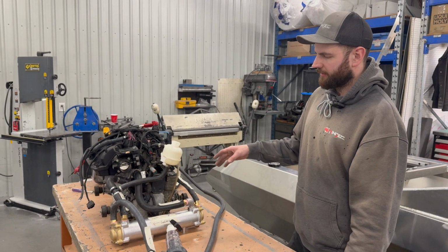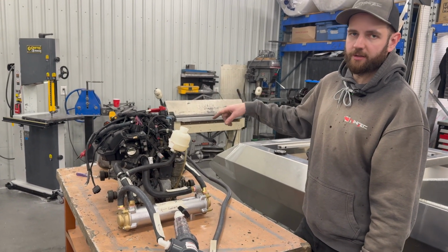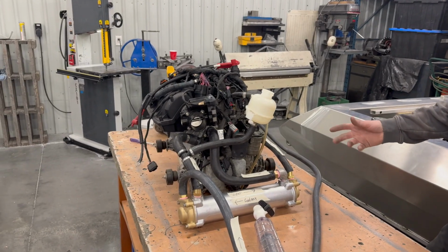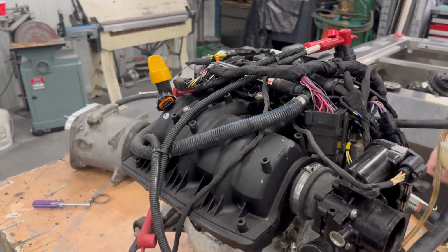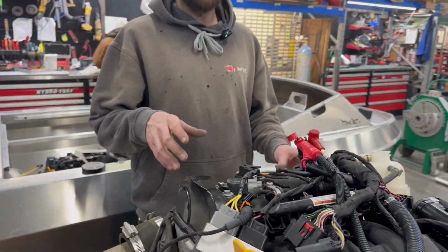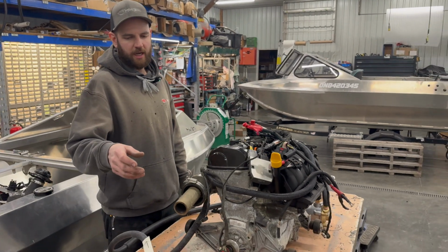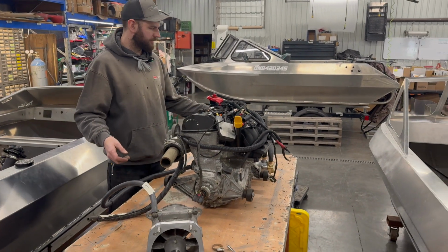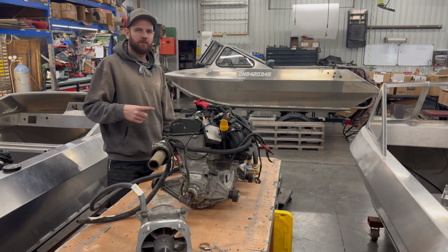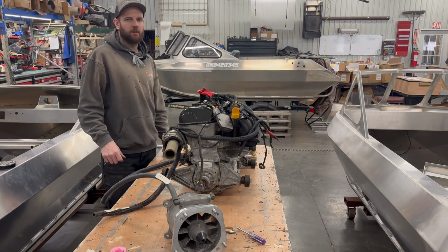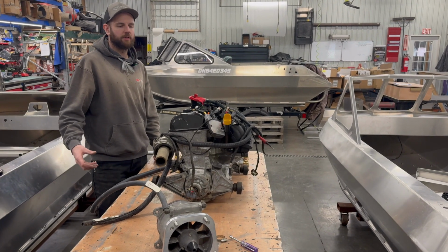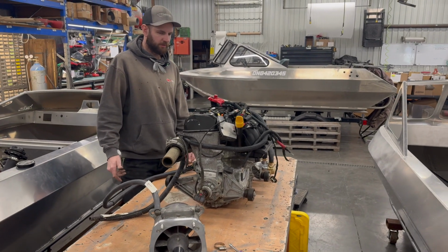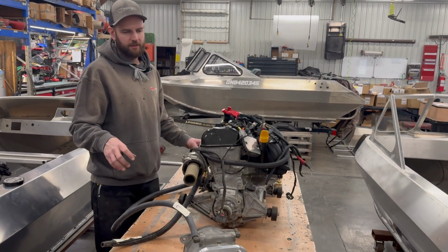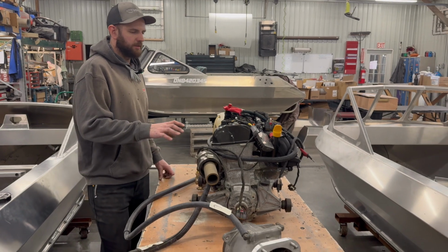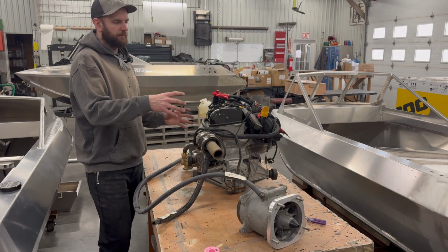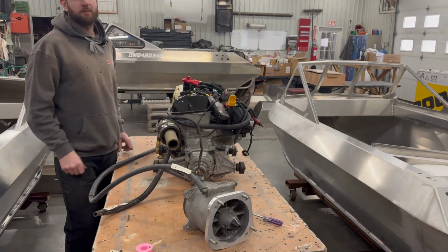So there are a number of different advantages. There's corrosion protection, since the coolant won't rust running through the aluminum block, so no corrosion issues inside. Also, because the coolant is always there, it can't run out. If you happen to plug up your jet pump or your sand trap, there's still always some coolant running through the engine, and that will protect it until your overheat sensors can step in and alert the operator that there's an issue. Also, for winterization, you only have to winterize the raw water side of the system. The engine always maintains that antifreeze property around all the critical expensive components to protect them.